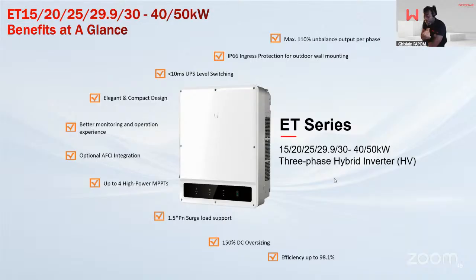They have optional AFCI integration, meaning that when you place your order, if you want the AFCI option, you can add it to the inverter at factory. Of course, once you've bought the inverter, you can add it later on. We have 4 high power MPPTs, a 1.5 power surge load, 150% DC to AC ratio, and a high efficiency of 98.1%.